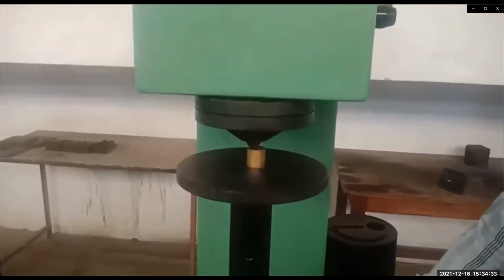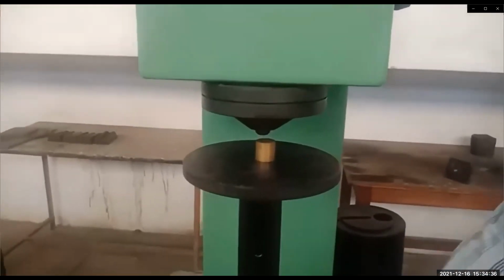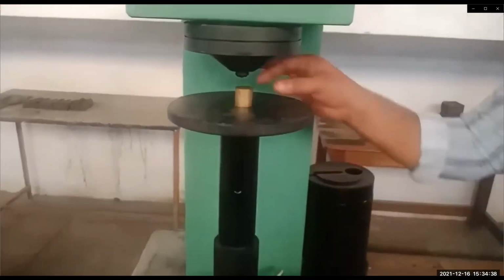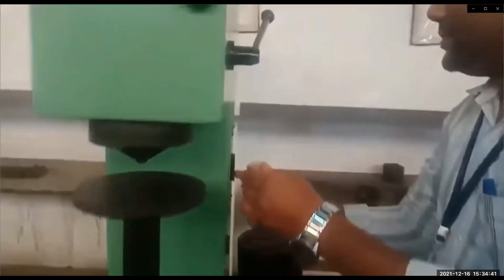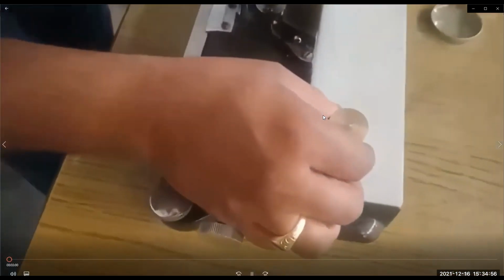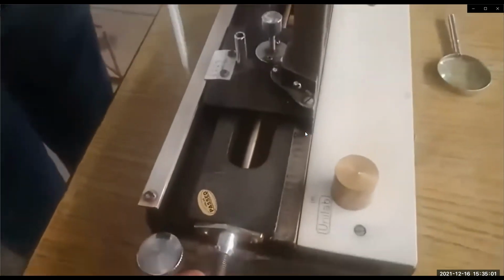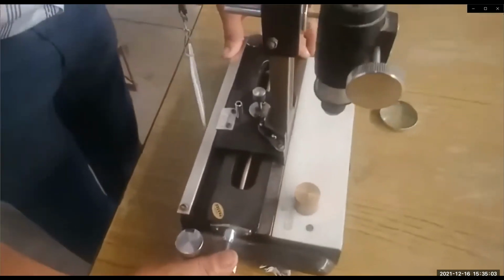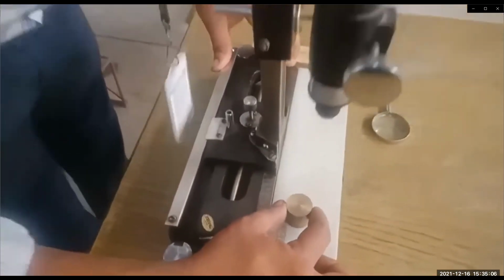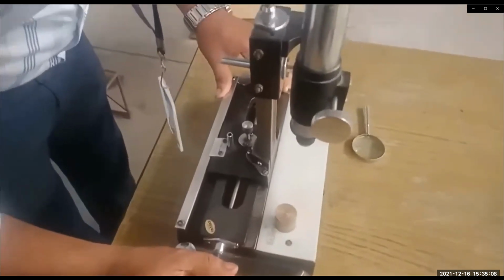Then, once again, in anti-clockwise rotation, we retract back the anvil, take the specimen and switch off the machine. Then an indentation mark should appear on the specimen. With the help of a chalk piece, we mark that. Once the mark is made on the indentation, with the help of the traveling microscope, we take the D1 value, diagonal 1, and in the other direction diagonal 2, then take the average value of that.